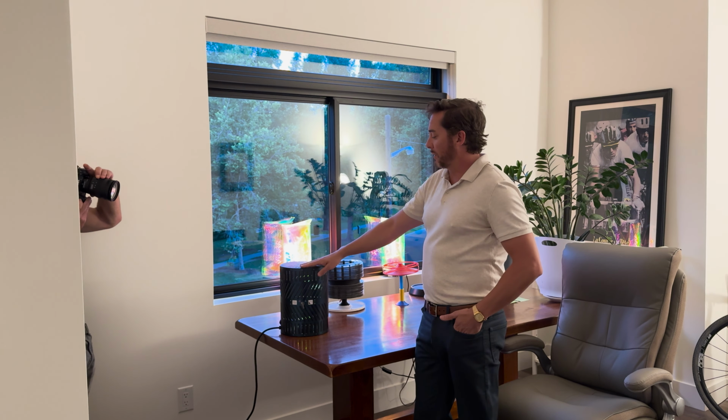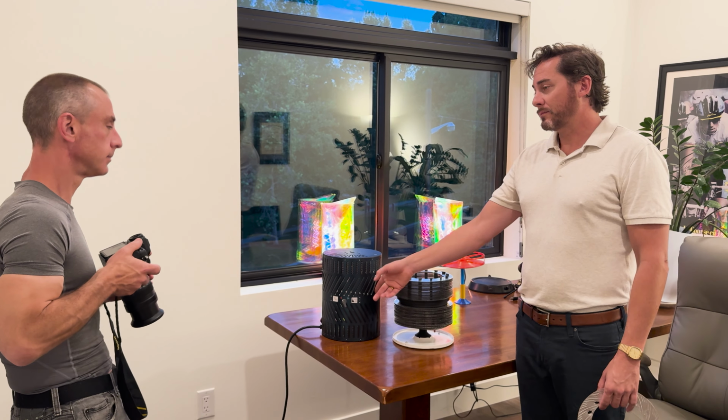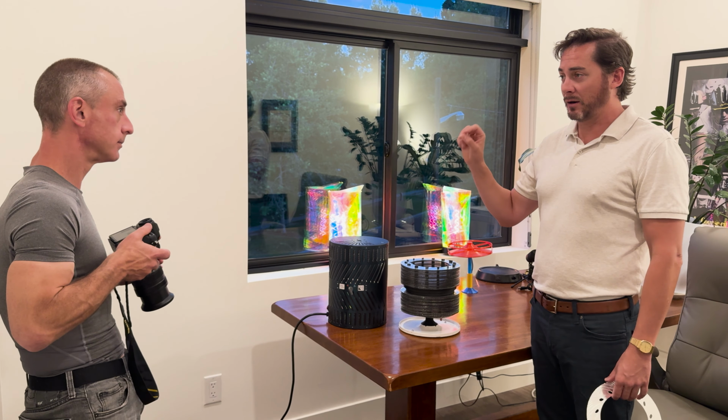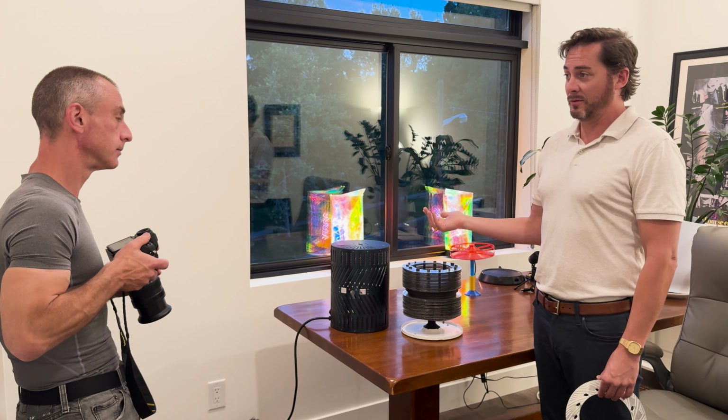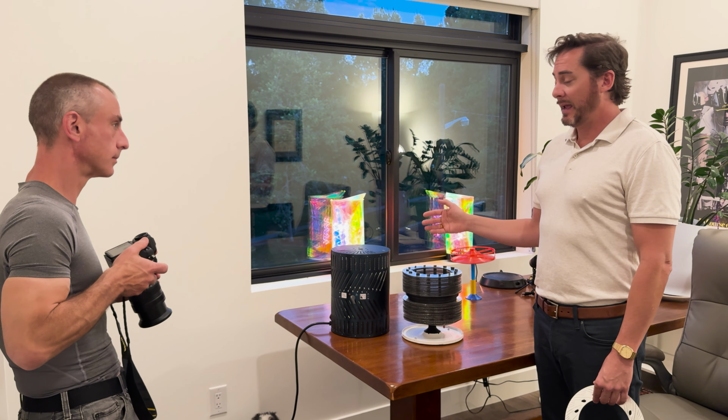So in testing, and this is where things get wild. We've been able to test this fan right here. It's very easy to test how much energy goes into it. It's very easy to test how much air comes out of it, and put that on the fan curve with a regular centrifugal blower. And when we compare it to the next most efficient centrifugal blower, this is twice as efficient.